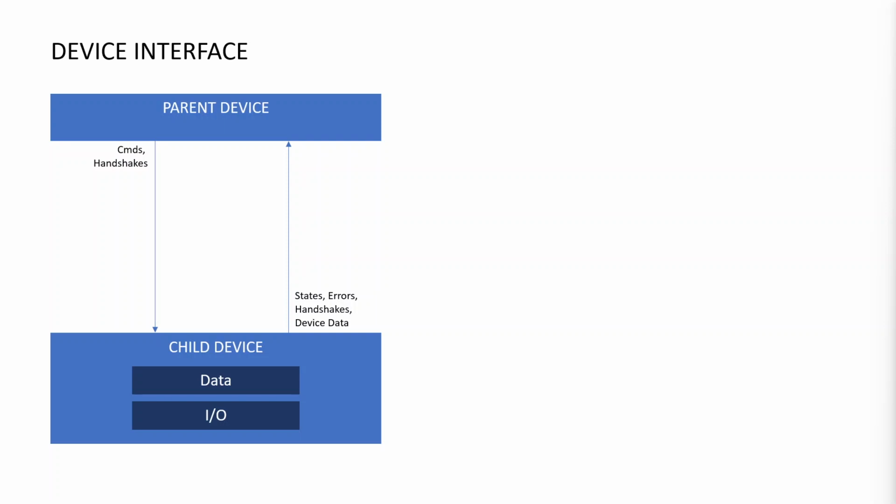The parent device would set the request handshake bit, the child device would react to that request and perform the duty. In a lot of cases, I believe we're issuing a change recipe request, and then the child device updates the recipe, says it's done updating the recipe, and then the parent would drop that handshake request. Those are the primary methods for issuing commands from a parent to a child.